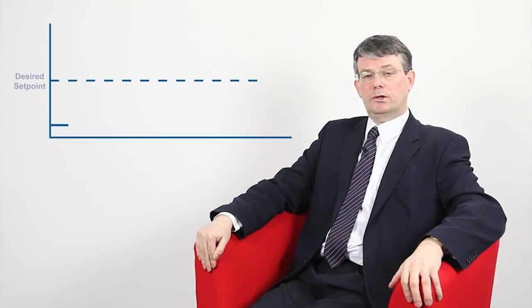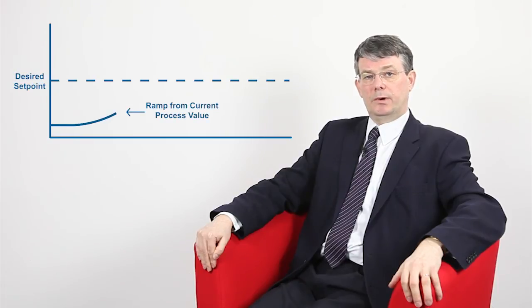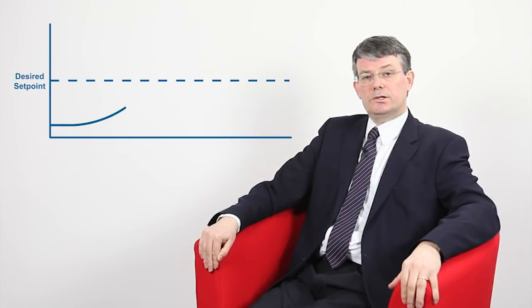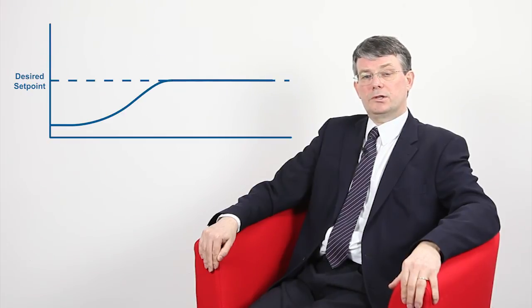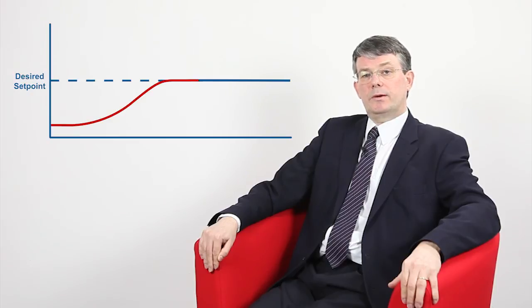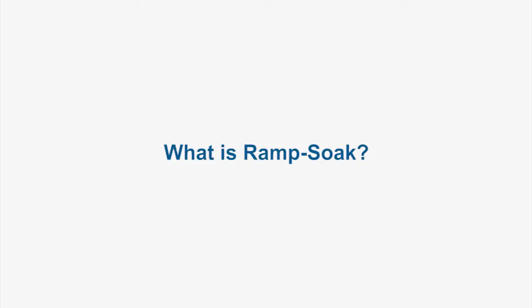To further protect the process, the ramp is also used at power up and when the controller is switched back from manual to automatic control. Under these circumstances, the process value is measured and used as the starting set point value, and from there the process is ramped up towards its final set point value at the rate set.